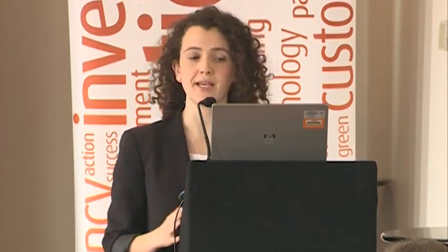One of the questions that have come up and that we still need to get our heads around is, because we're talking about reinforcement, we all want to understand when reinforcement happens, and how can we do our reinforcement and operate our network more optimally? There are essentially two things that can trigger reinforcement. The first one, which is pretty straightforward because we're used to that, is demand-triggered reinforcement. So load growth: as we develop and there's more generation and demand in a certain part of the network, eventually it gets to a point where we have to reinforce due to demand growth.